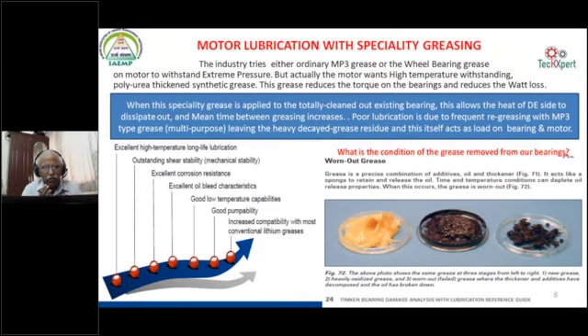If a motor is fitted with a specialty grease, I have seen this especially in the textile mills. Here I should say, in textile mills we have done more audits, around 300 audits out of about 400. That gave us a lot of technology inputs on where all the energy can be saved or conserved. This is what I want to share with other industries. Some motors are still using this multi-purpose grease, and I have seen some industries pumping every week, every month, every 3 months, every 6 months.